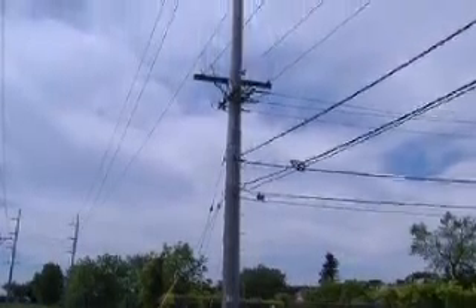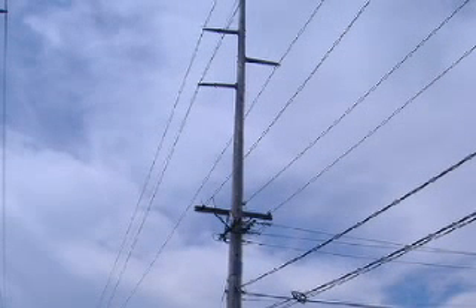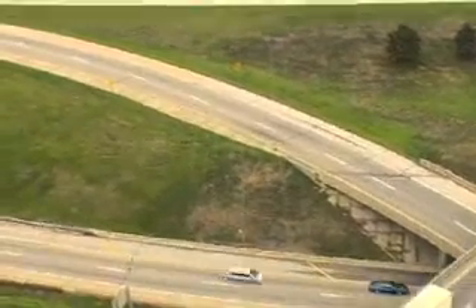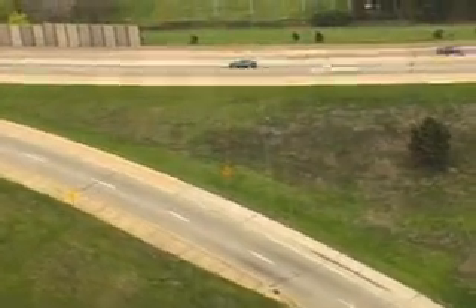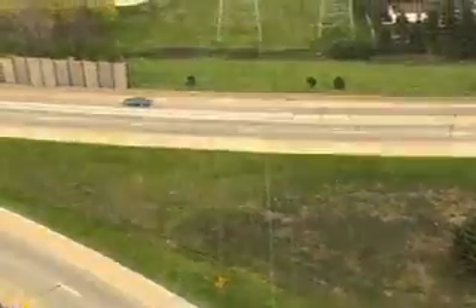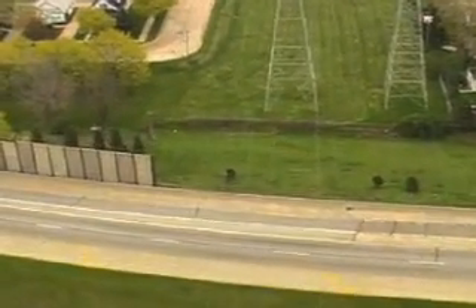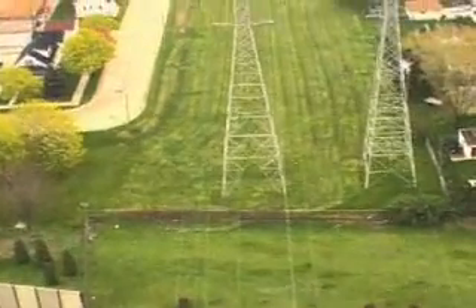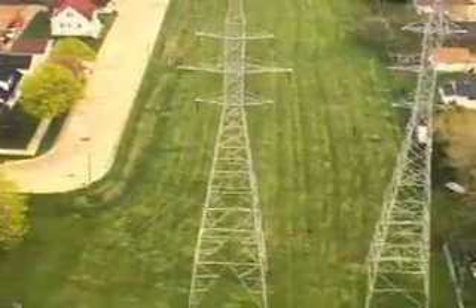Electric distribution and communication utilities that attach their facilities to transmission poles must be mindful of pole loading and clearance requirements. If the transmission structure wasn't designed to hold additional facilities, adding them may overload the pole or cause a clearance violation. All attachment requests must be reviewed and approved prior to attaching to the transmission facilities. The ATC transmission system operates 24 hours a day, 7 days a week, so our crews need to be able to access it at all times. It's very important for our rights-of-way to be clear of obstructions should there ever be a need to restore the system or perform regular maintenance.